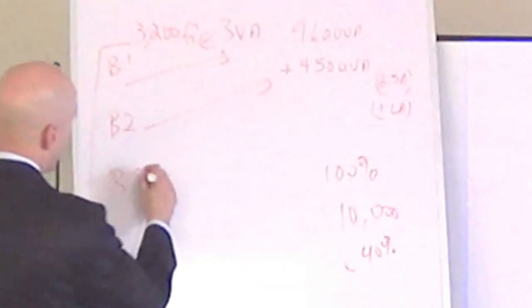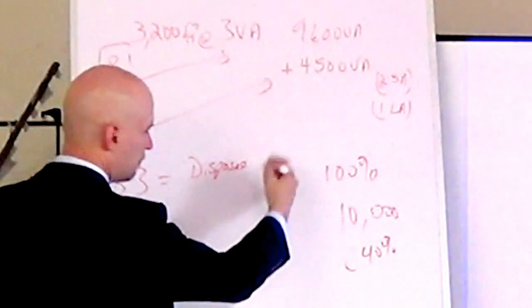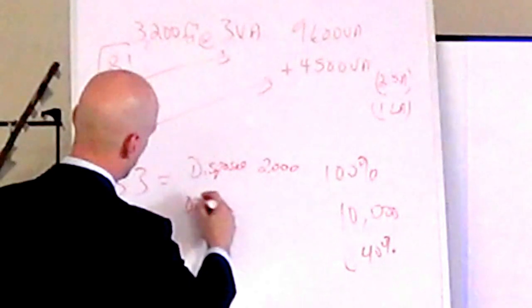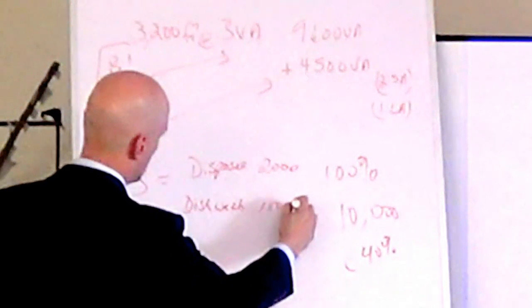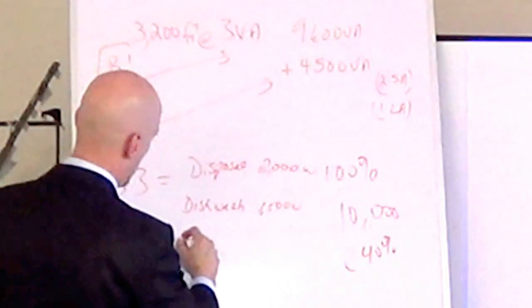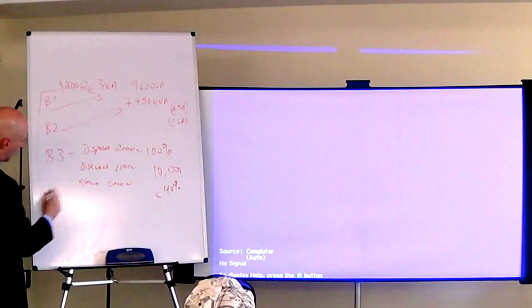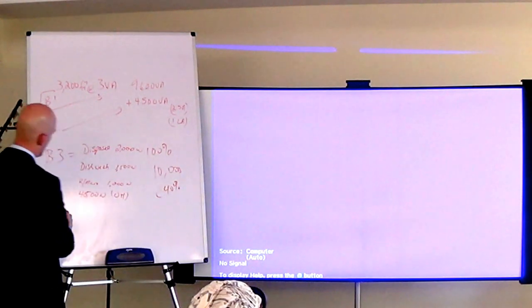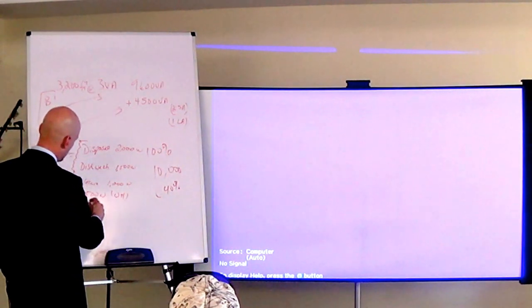So we're going to add in, in this case, that we had fastened-place appliances. Let's just say that we had a disposal that was 2,000-watt disposal. And then a dishwasher that was 1,500, a range micro combo that was 1,200. And then water heater at 4,500. All right, so these fastened-place appliances here all go under B3 and then A, B, C, D. If we had a range, which we'll add in here at 8,000 for the range and a dryer for 4,500.